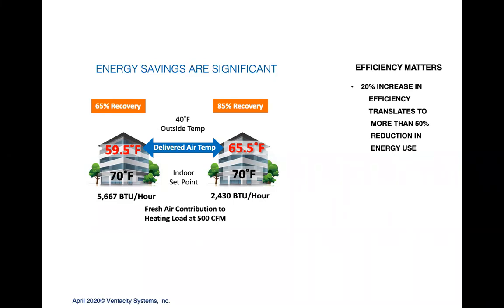So we're looking at 500 CFM here, which would be one classroom in a school, one modest-sized office, one modest restaurant. At 500 CFM, to bring 59.5 degree air up to 70 degrees would require 5,600 BTUs an hour. If you bring it in at 65.5 degrees, it's only 2,400. So there's about 150% more energy for that 20% difference in efficiency. So this is where very high efficiency heat recovery has a very big impact.